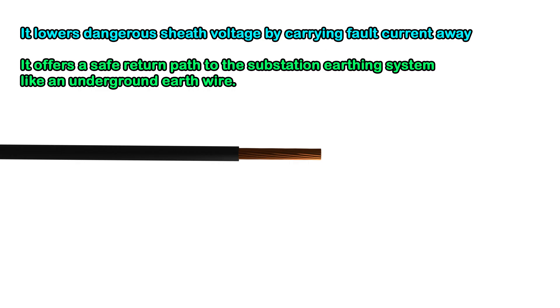Sizing the ECC correctly is critical. For example, in a 220 kV system with a 40 kA short circuit lasting 3 seconds, the ECC must handle that current for the full duration without damage.